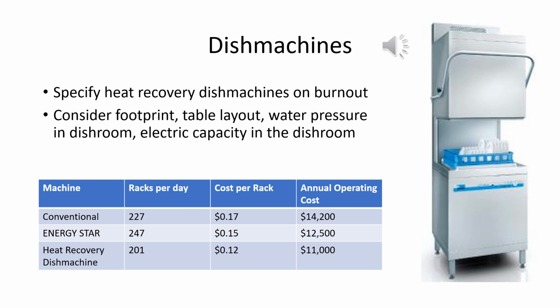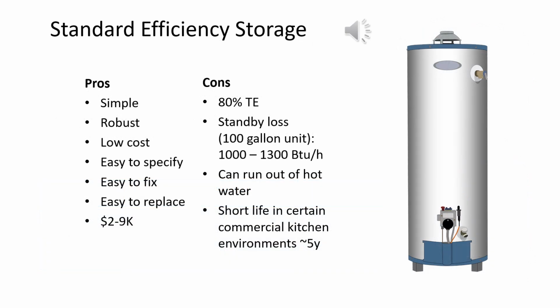A common problem when switching from a low temperature rinse dish machine to a high temperature rinse dish machine is that there is not enough power in the dish room to operate the new machine, which requires an electrician to run new electrical line from the main breaker and sometimes to install a subpanel. The first step in selecting a water heater for a commercial food service facility, once the rest of the system is designed, is to select the kind of water heater that is desired.